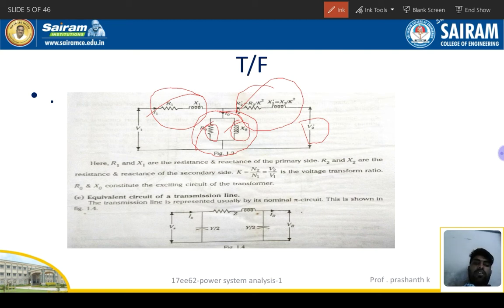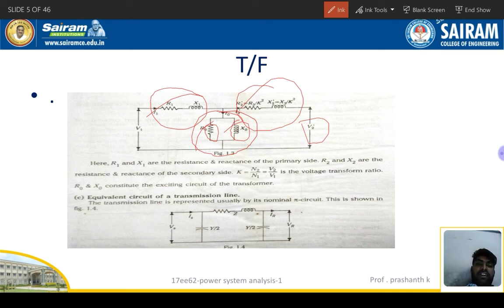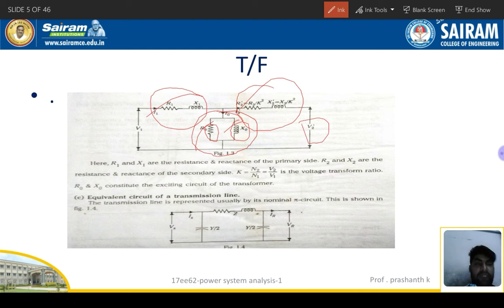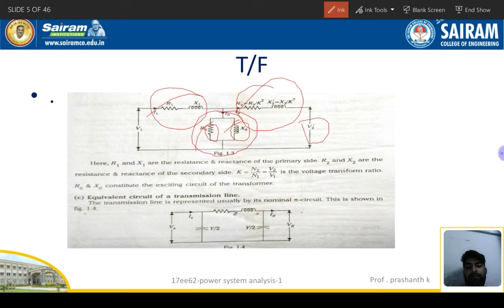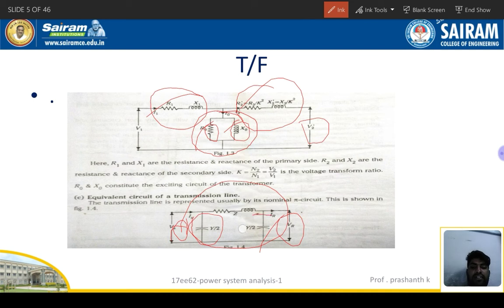Next, we have the equivalent circuit of transmission lines. There are two types: T model and pi model. Transmission lines are also classified by length: short transmission lines are less than 80 km, medium transmission lines are 80 to 250 km, and long transmission lines are above 250 km. The pi model looks like the Greek letter pi, with a capacitor present at the source side and at the receiving end side — this represents the charging admittance.